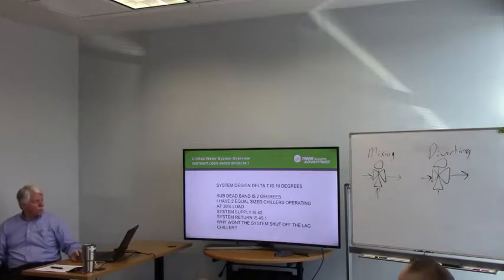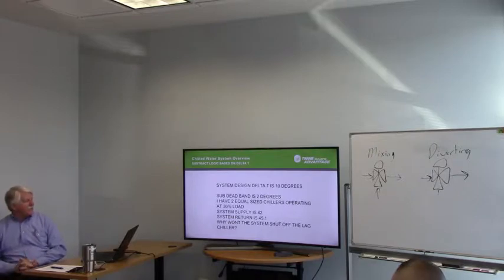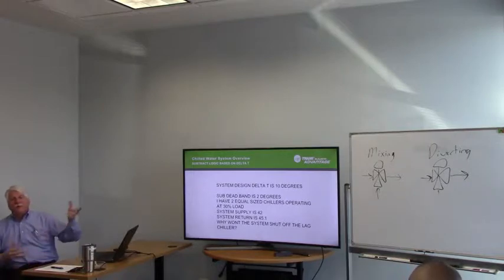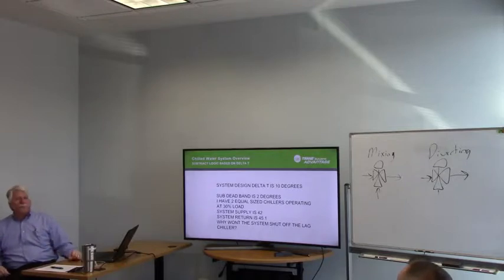Now, what we're looking at here is a system delta T of 10 degrees. And in chiller plant control, you have to tell it the system design delta T, the subtract deadband, and then the chiller size so it can calculate what's going on. So I have a system that was running under pretty heavy load. I had 2 chillers running. And right now, both chillers are running at 30% load. The system supply is 42. The system return is 51.